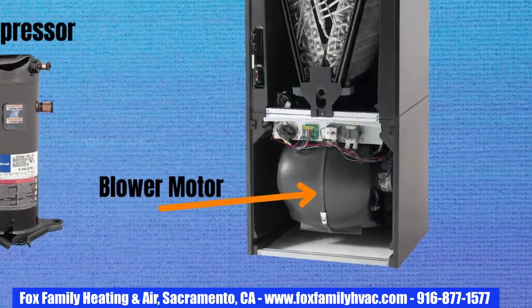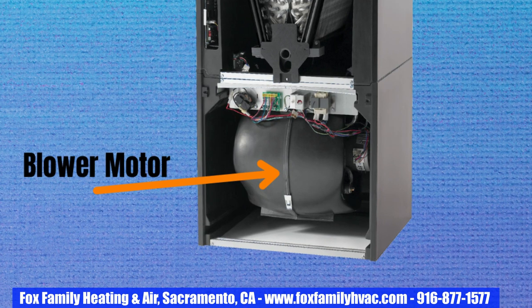Motors are more efficient when they run at lower speeds. A 3-ton air conditioner blower motor will run at one amperage, while a 5-ton bigger blower motor, with its speed taps adjusted down to a 3-ton capacity, will run at less amperage than the 3-ton motor. That lowers the amount of energy used by the system, increasing its SEER rating.